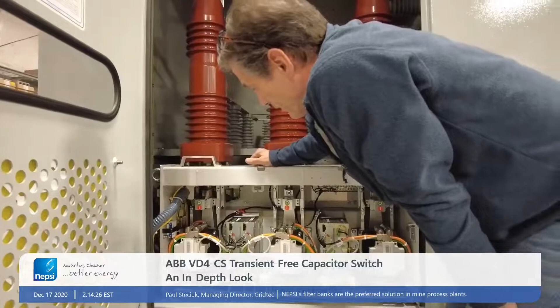Why don't you talk about the indicators? There's three indicators here because these are independent poles, closed independently. They're not mechanically linked to one another. There's an indicator for each pole. So when this breaker operates, this mechanism will go up and down, and it'll tell you whether it's closed or open.